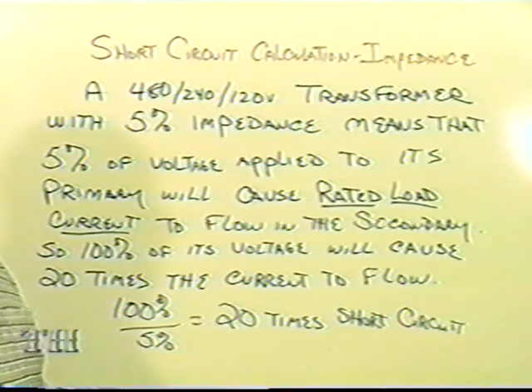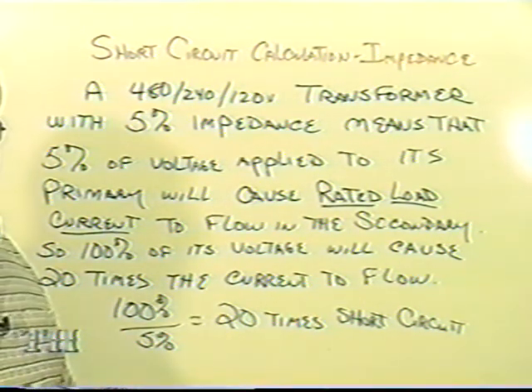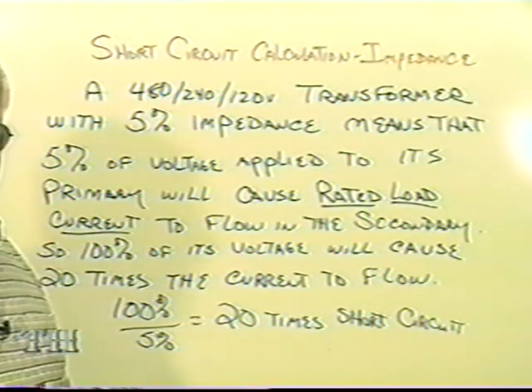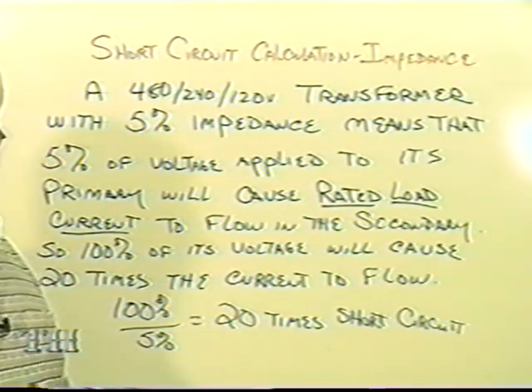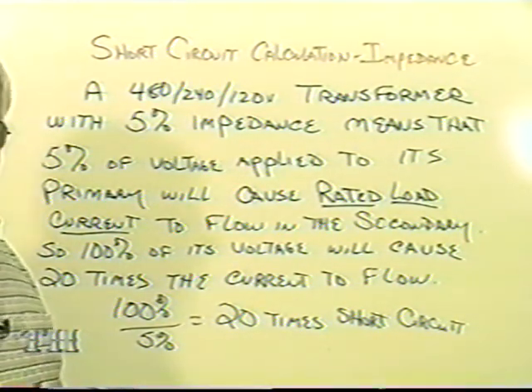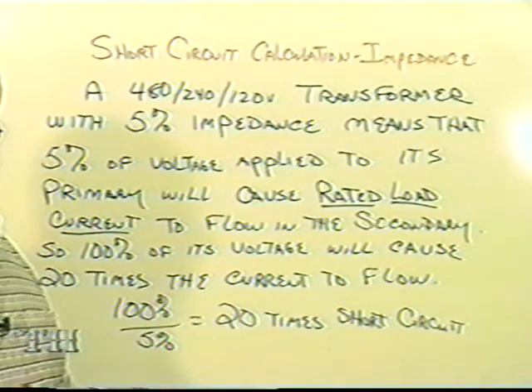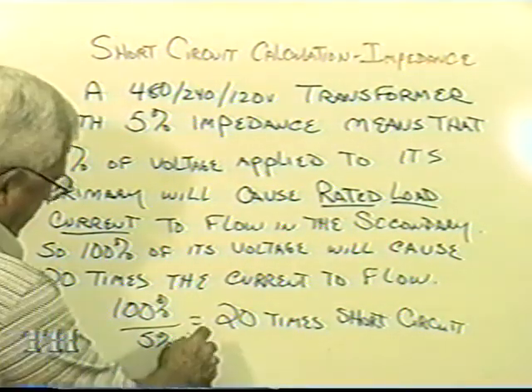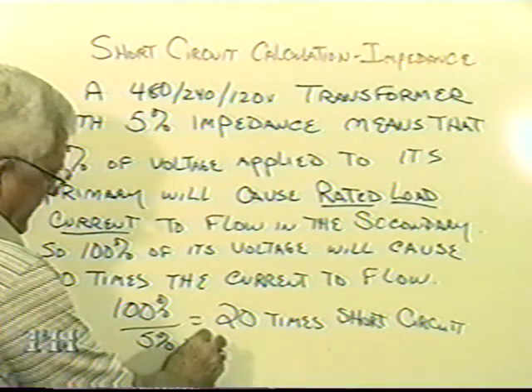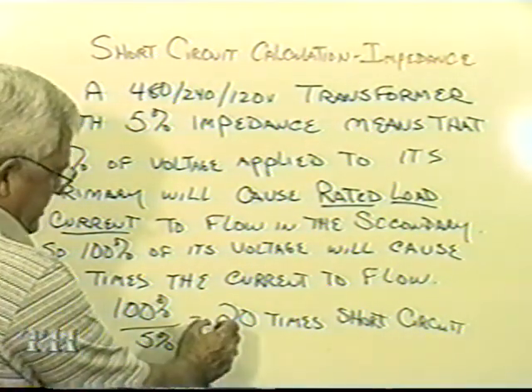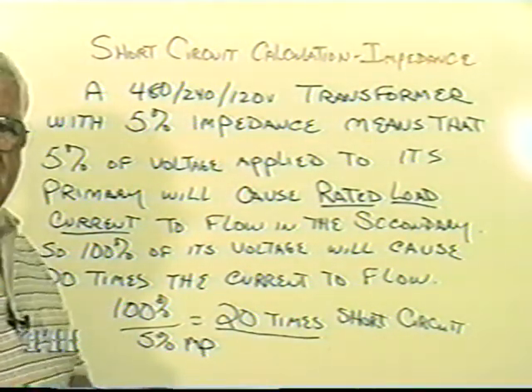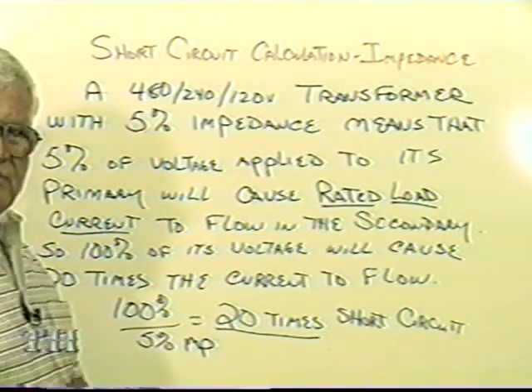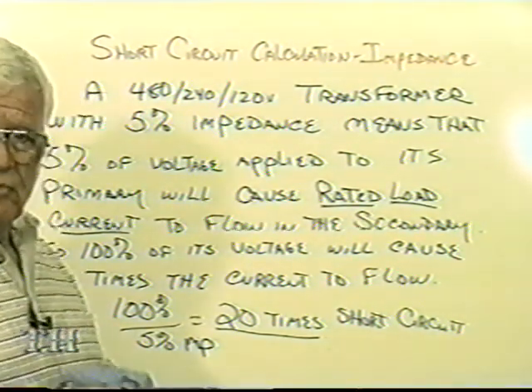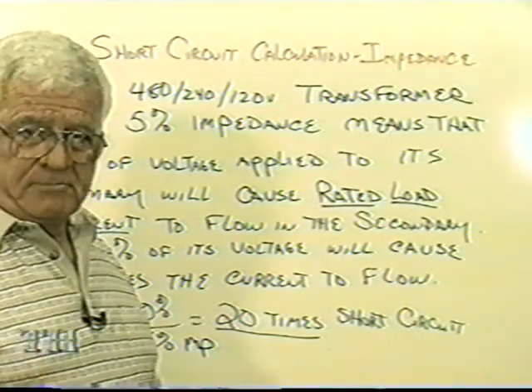And I'm moving out of the way so you can read it. It'll say the primary, if I apply 5% of the voltage to the primary, will cause the rated load current to flow in the secondary. So 100% of its voltage will cause 20 times. So all you're doing on these calculations is taking the 100% and dividing it by whatever the impedance is. And that'll tell you in this case you would have 20 times the short circuit current, which is the stuff that blows the panel boards off the wall and warps the bus bars.